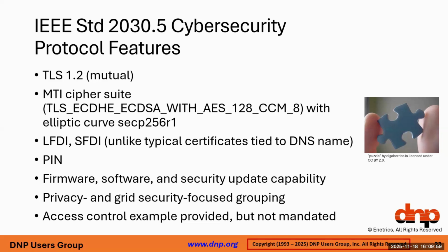Some other components: we have an LFDI and an SFDI, a long form device identifier and a short form device identifier. Those are essentially different sized hashes of a device's certificate, used for identification purposes. This matters because in a normal internet world, a certificate contains a DNS name cryptographically signed, like google.com. But devices like the DER we're dealing with in 2030.5 won't have a DNS name, and probably won't have a static IP address either. So you need a way of tying an identity to that certificate, and that's where LFDIs and SFDIs come in. When you register a device with a utility, you give them that LFDI, which ties it in a secure fashion back to the certificate because it's a secure hash.